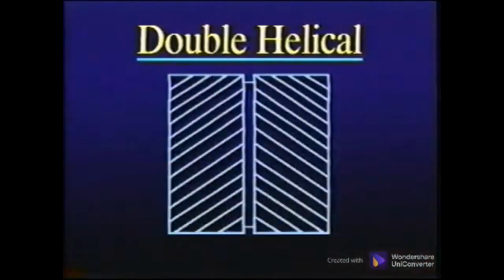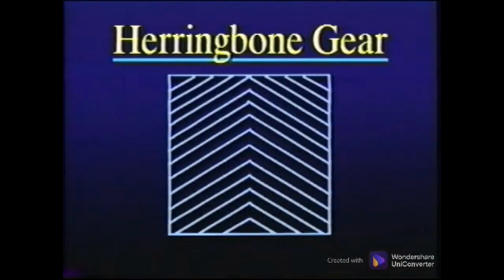The primary disadvantage is the slanting or spiral tooth design creates strong axial vibrations, which is rarely seen in spur gears. Some applications use a double helical configuration, which is essentially two helical gears back to back. These can be placed on the shaft in such a precise location that the axial forces cancel themselves out. When two sets of helical teeth are cut on the same gear and intersect each other, they are called a herringbone pattern.